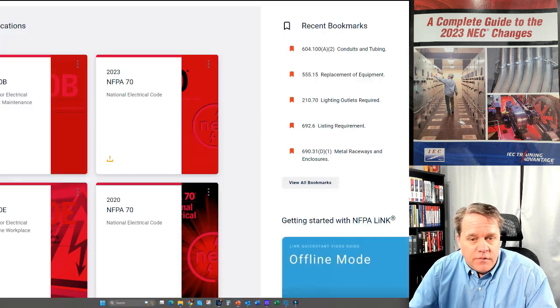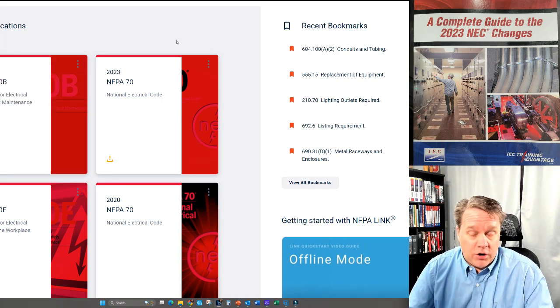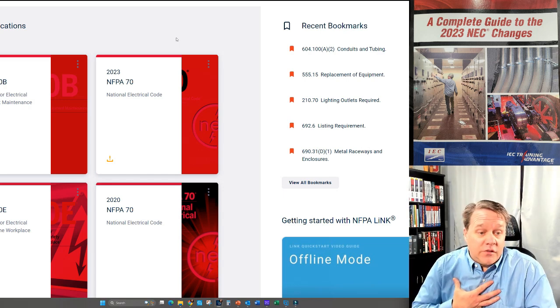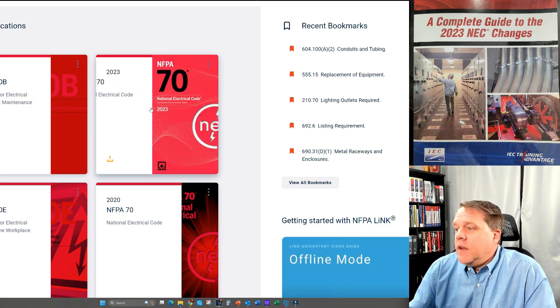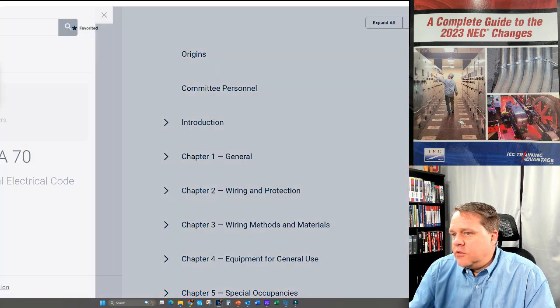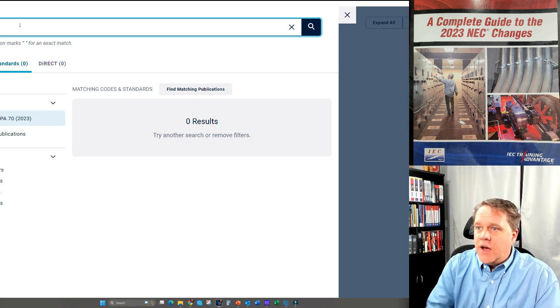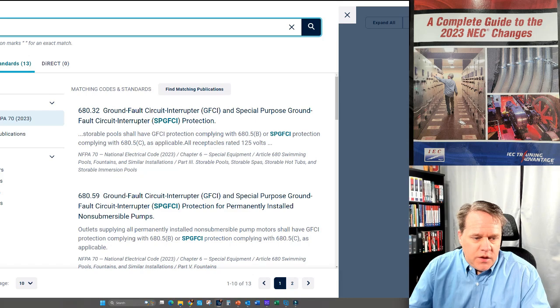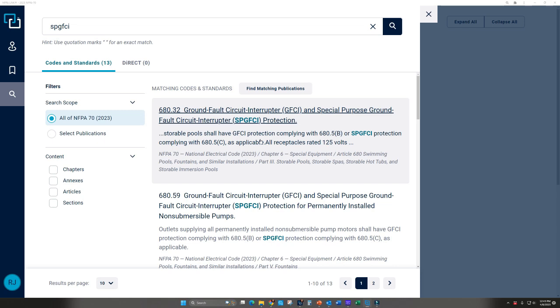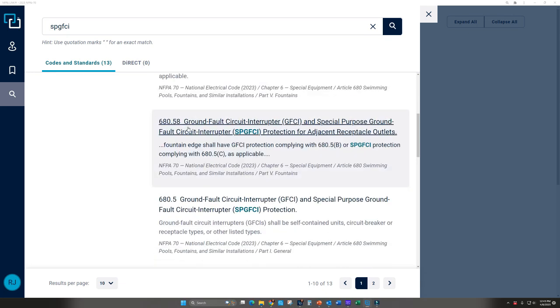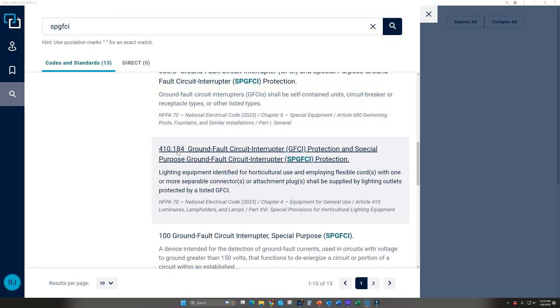Opening NFPA Link — I'm not trying to sell it, but I have to have it. In the 2023 NEC, searching for 'SP-GFCI' or 'special purpose GFCI' shows where the requirements appear. As you can see, almost all of them are in swimming pools. We're not requiring SP-GFCI throughout houses or for receptacles in bathrooms or outdoors — these are very limited applications. Article 680 — swimming pools — dominates the results: 680.32 and several other 680 sections.